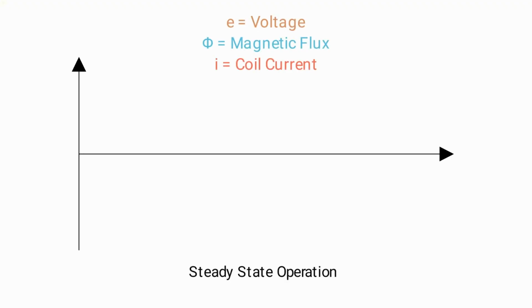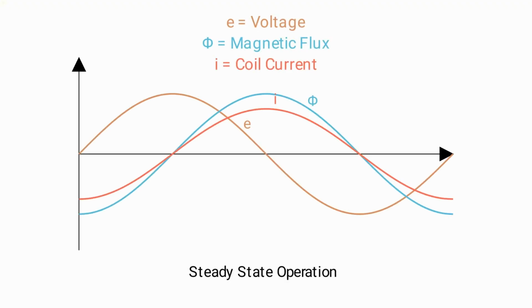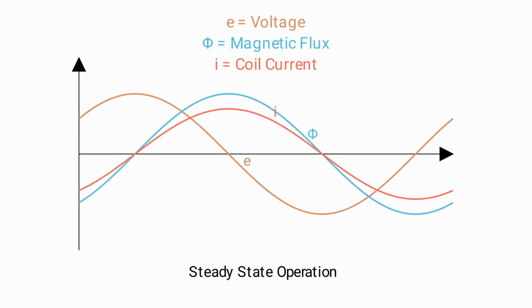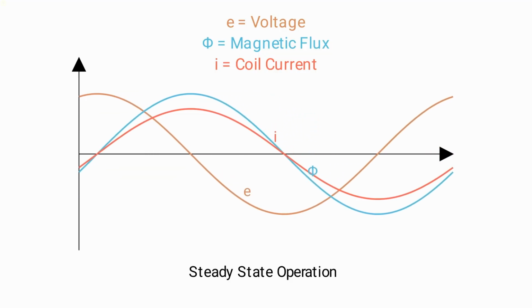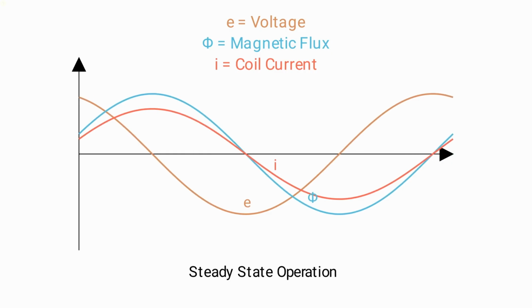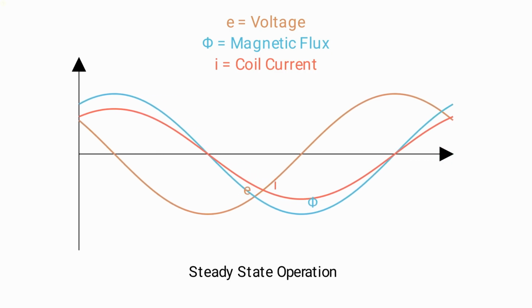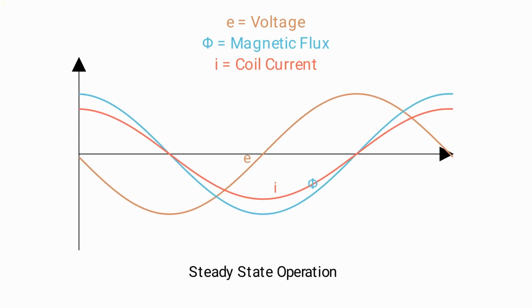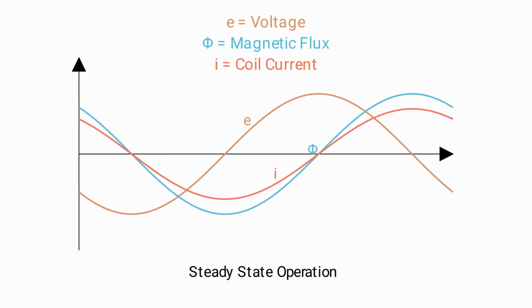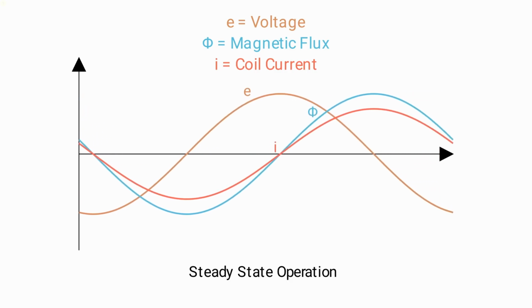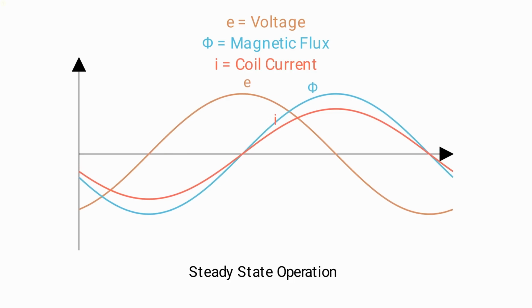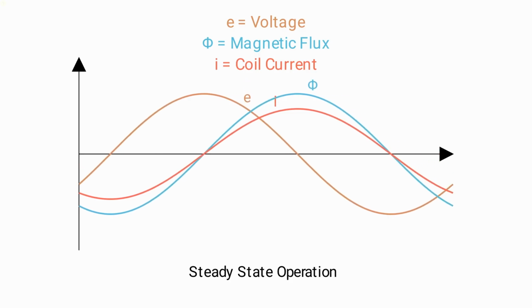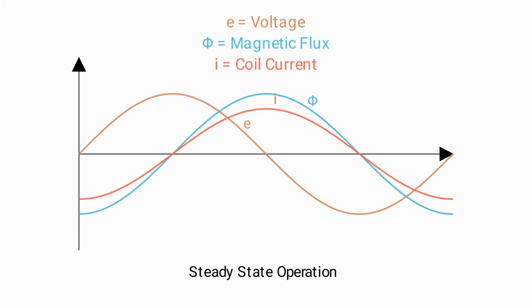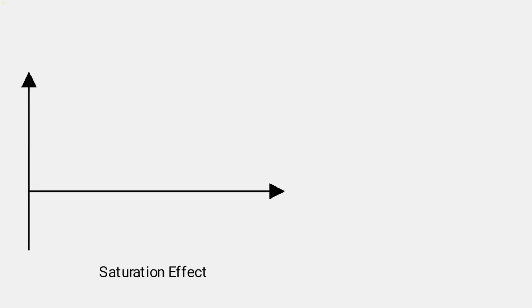Let me tell you more about what causes this inrush current. When a transformer is switched on, it doesn't immediately behave normally. It first has to build up a magnetic field, what we call a magnetizing flux. The problem is, how that flux builds up depends on when in the AC cycle you switch it on. If you happen to switch it on at an unlucky moment, like near a zero crossing, the flux can overshoot.